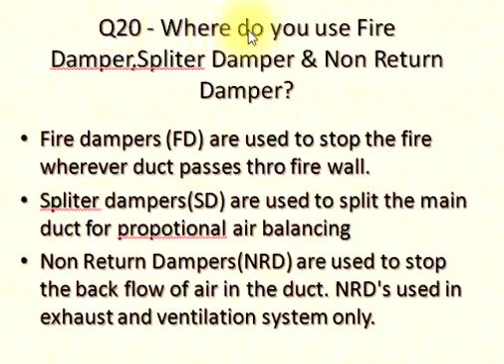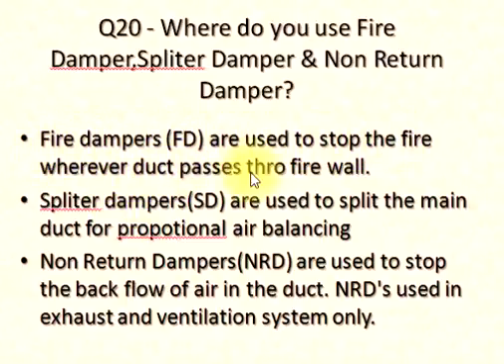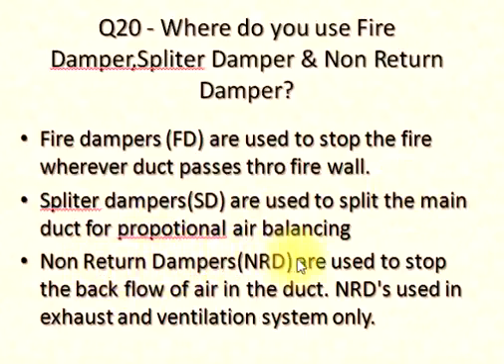Q20: Where do you use fire damper, splitter damper, and non-return damper? Fire dampers (FD) are used to stop the fire wherever a duct passes through a fire wall. Splitter dampers (SD) are used to split the main duct for proportional air balancing. Non-return dampers (NRD) are used to stop the back flow of air in the duct. NRDs are used in exhaust and ventilation systems only.